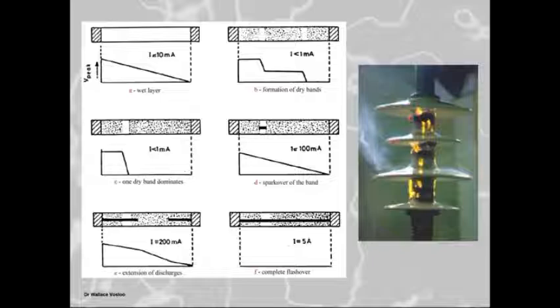So the insulator is beautifully clean and there's no pollution there, and now suddenly a conductive fog comes in. Fog is normally formed where you've got a particle, and around the particle the moisture condenses. If it's a clean particle, it's a clean fog. If it's a little salt crystal, it's a salt fog. If it's an industrial pollution particle, it's an industrial fog. These fogs then form an electrolytic layer instantaneously across the surface of this insulator. So there was this insulator you cleaned yesterday, and today it is polluted. But what both pollution types have in common is that they form a conducting electrolytic pollution layer over the surface, okay?